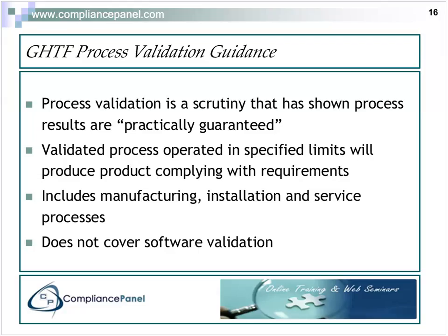Service process is in a very similar manner. A company comes in to service a product. We want to make sure that before we expose patients to that product once it's been serviced, that in fact that product does meet the requirements and will not harm the patient.